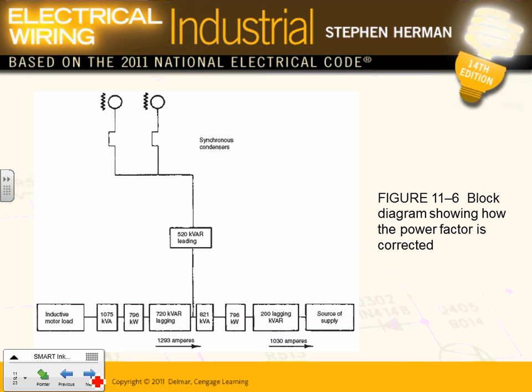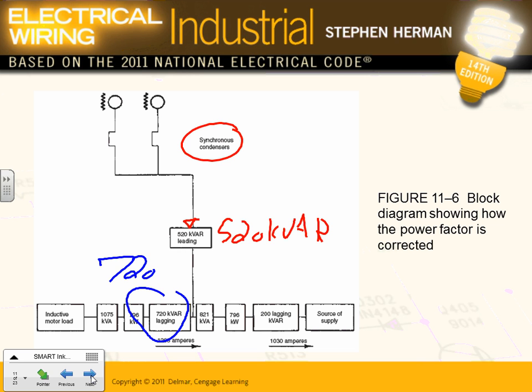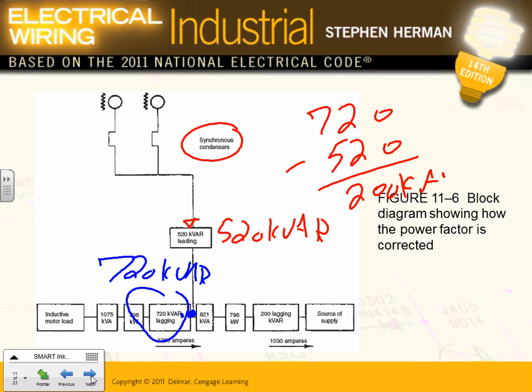Here's a very good example, guys. I have two synchronous condensers. Together, they're generating 520 kVAR. What I would like you guys to look at is right here. So here's the power that I have in my building. Let's look at the VAR here. Here's my VAR. I have 720 kVAR, and I'm injecting right at this point, correcting the power factor. So look what happened: if you have 720, subtract 520 from that. That will leave you with 200 kVAR, right? And this is what's left over after I corrected the power factor.